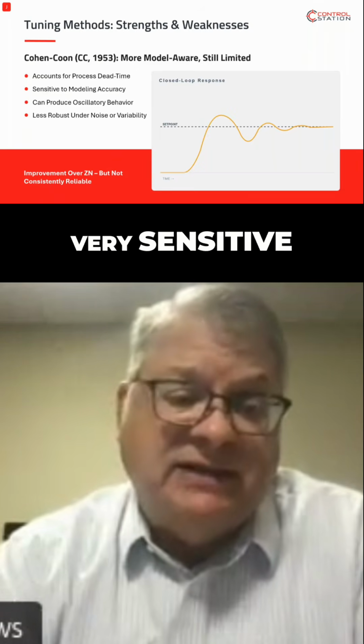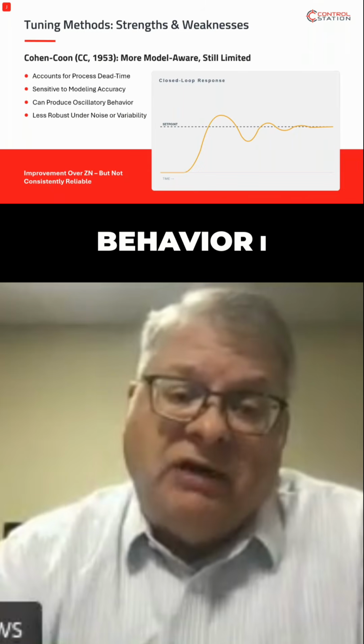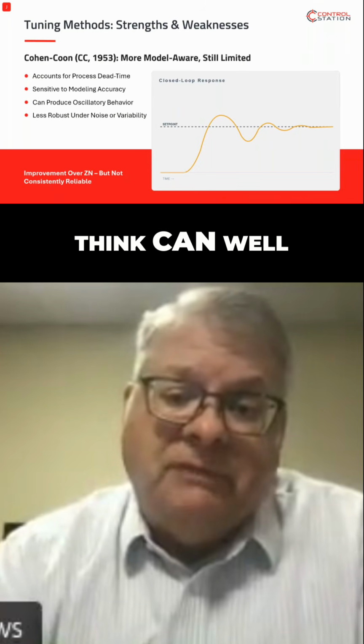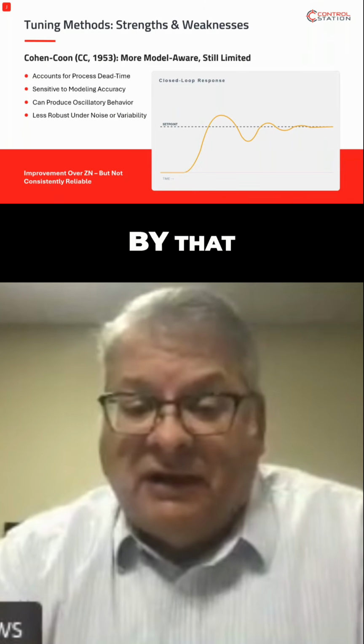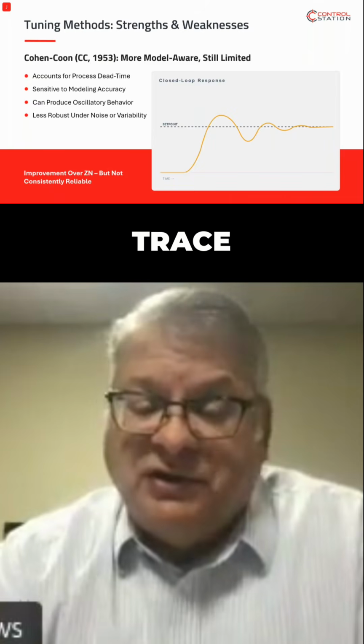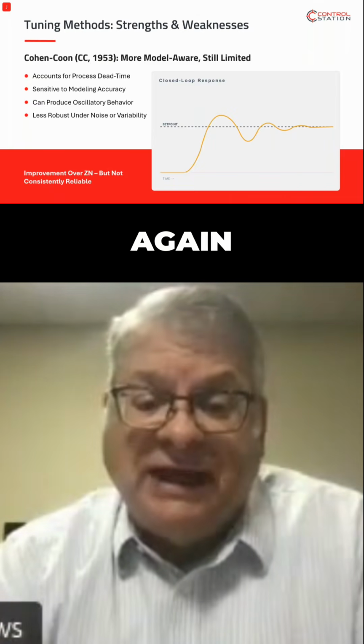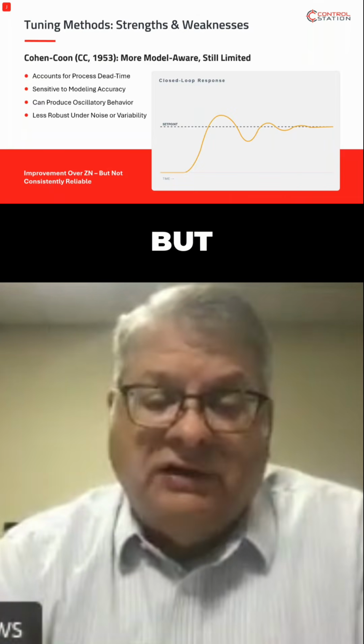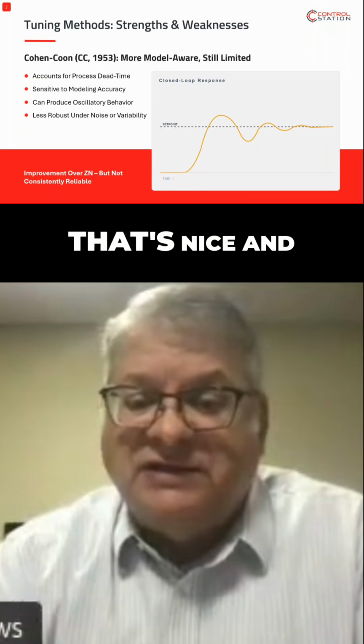Cohen-Coon is very sensitive. That oscillatory behavior, I think, well, you can see there by that computerized trace, you can see that there is quite a bit of oscillation. Again, not as bad as Ziegler-Nichols, but it's not giving us something that's nice and steady.